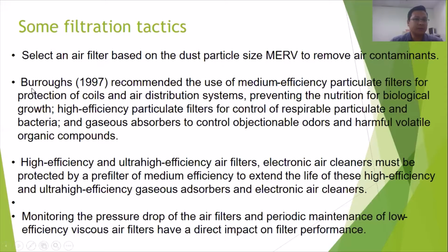The second one, Burroughs recommended the use of medium efficiency particulate filter for protection of coil and air distribution system, preventing the nutrition for biological growth, high efficiency particulate filter for control of respirable particulate and bacteria, and gas absorber to control objectionable odor and harmful volatile organic compound.